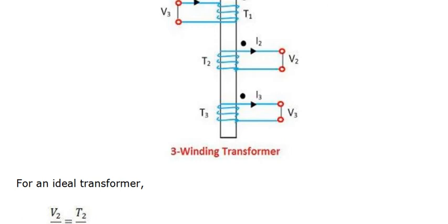It is to be noted that unbalanced and third harmonic problems do not arise when one or both sets of windings are connected in delta. Tertiary winding transformers are currently being manufactured with tertiary VA rating up to 35% of the total VA rating of the transformer.